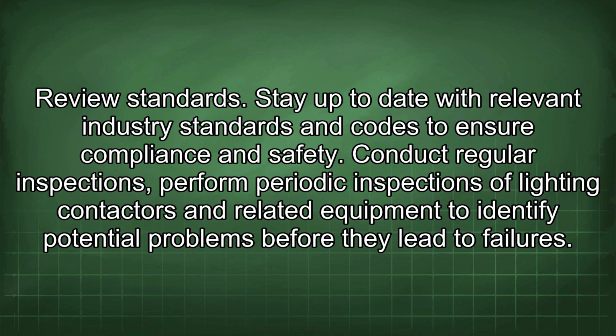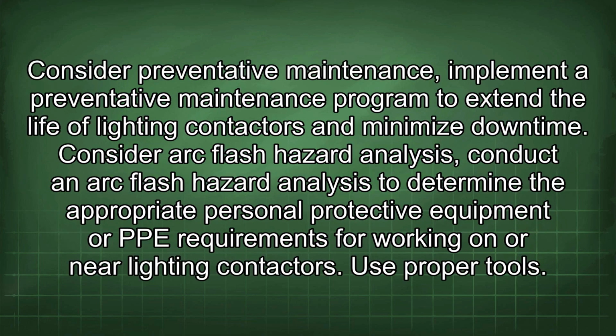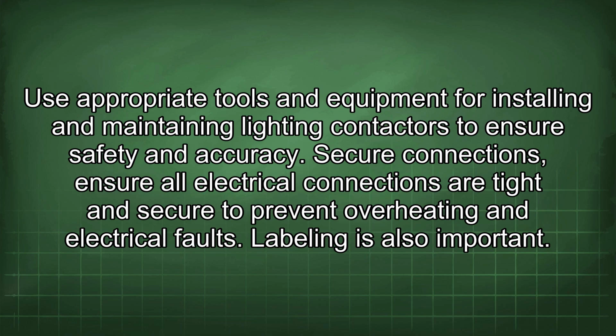Review standards. Stay up to date with relevant industry standards and codes to ensure compliance and safety. Conduct regular inspections. Perform periodic inspections of lighting contactors and related equipment to identify potential problems before they lead to failures. Consider preventative maintenance. Implement a preventative maintenance program to extend the life of lighting contactors and minimize downtime. Consider arc flash hazard analysis. Conduct an arc flash hazard analysis to determine the appropriate personal protective equipment or PPE requirements for working on or near lighting contactors. Use proper tools. Use appropriate tools and equipment for installing and maintaining lighting contactors to ensure safety and accuracy.